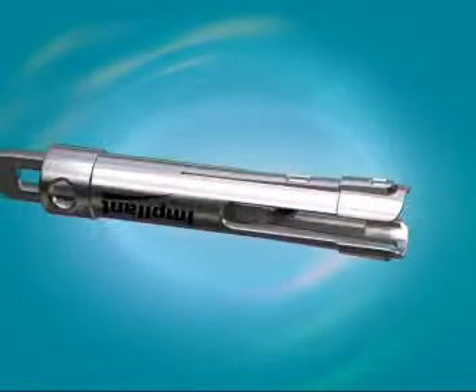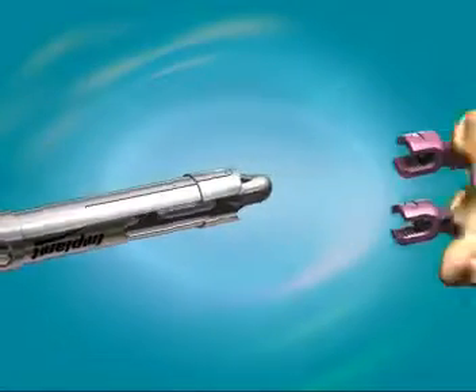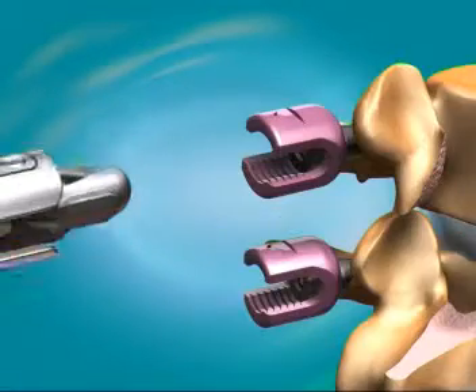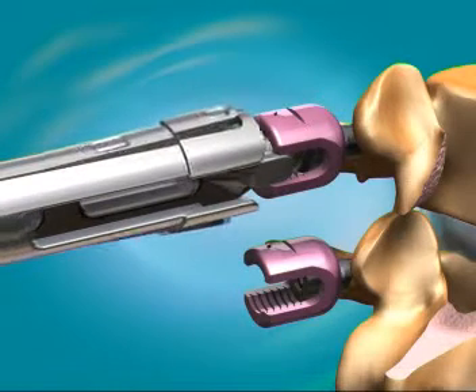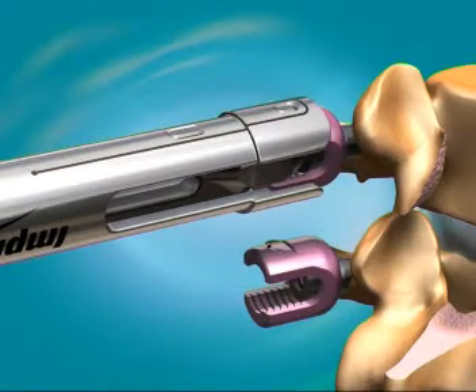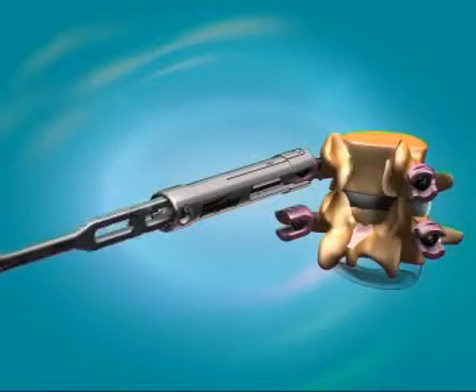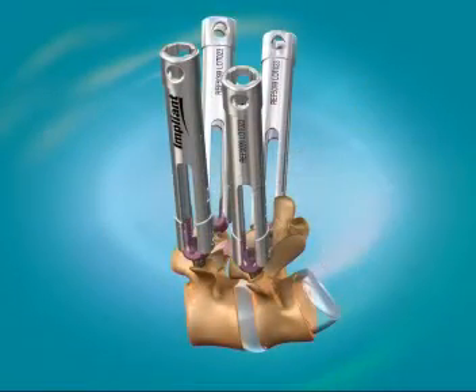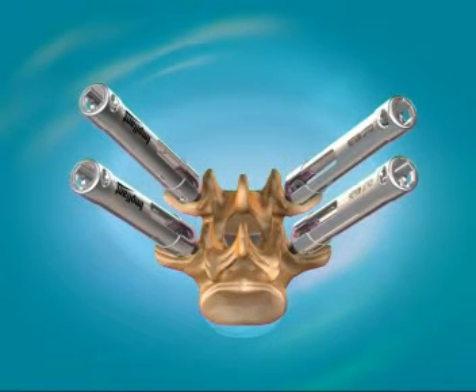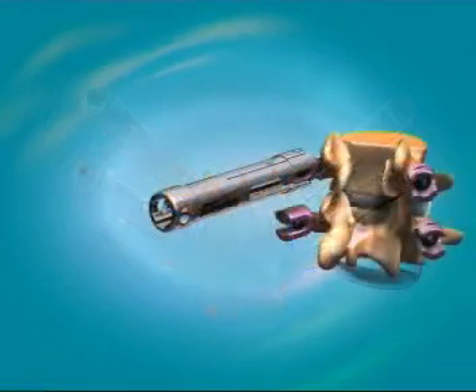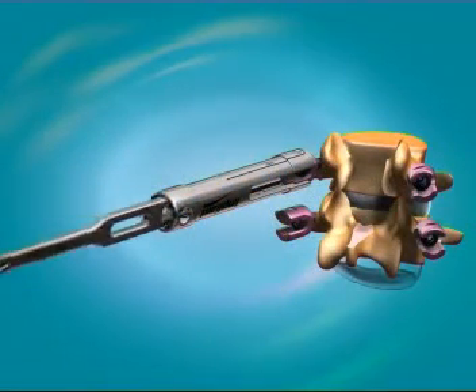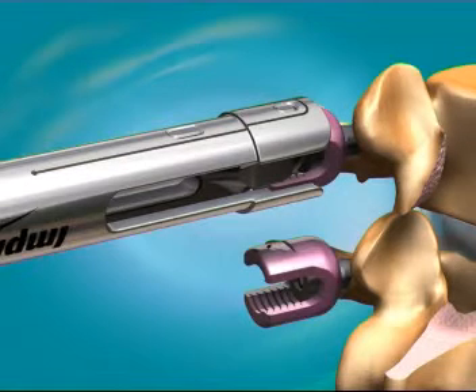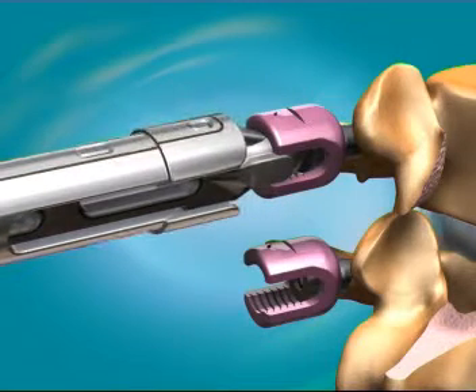Mount the pedicle screw guide onto the screw finder. Locate the pedicle screw head with the finder. Slide the pedicle screw guide down until it can no longer be advanced. Remove the screw finder and verify that the screw guide is locked onto the pedicle screw head. Note that locking occurs only after the removal of the finder. You can mount or dismount the extenders during the operation. If you want to remove one or more of the screw guides, insert the screw finder into the pedicle screw guide until it stops. Slide the guide upward until it releases from the pedicle screw.